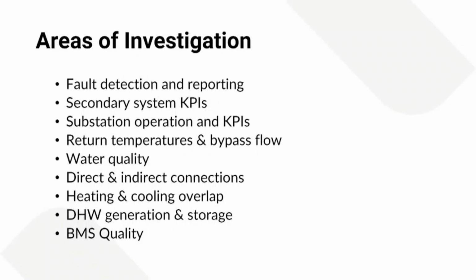So the areas we investigated were the fault detection of the systems and any reporting involved, and the secondary system KPIs — what's the system supposed to do, how's it supposed to deliver heat to the end client? Every client has a different need for the heat. If it's domestic, you're looking at HIUs. If it's a library, they've got to keep the heat within certain parameters to avoid too much humidity. So every different connection to the network has a different way of using the heat delivered to it — some want water at 100 or 105 degrees C, some want it at 70 degrees C. How do you do that when you're all connected to the same network? So it's interesting looking at the secondary systems and the KPIs in place for that.